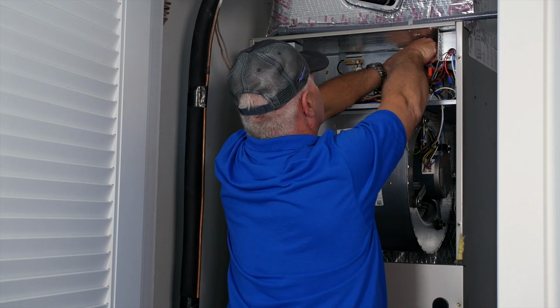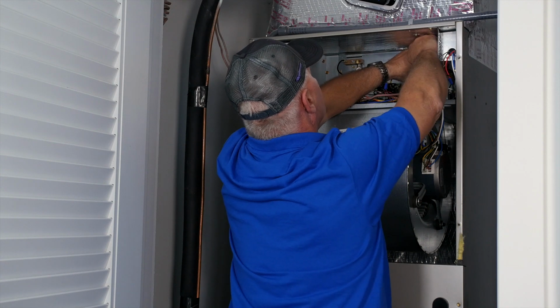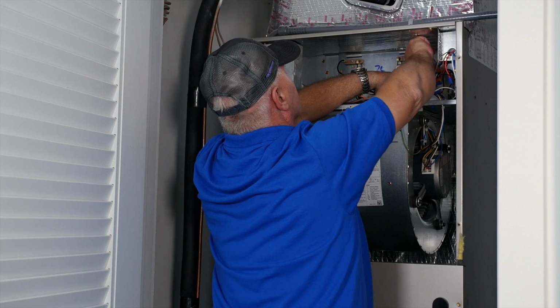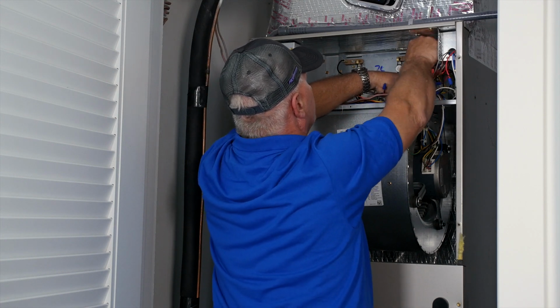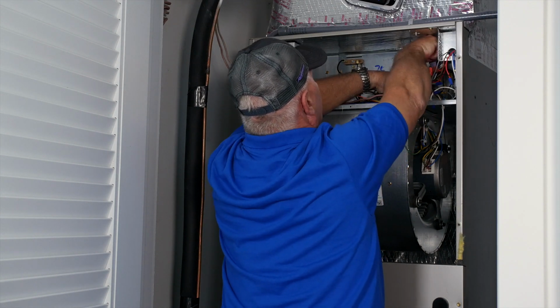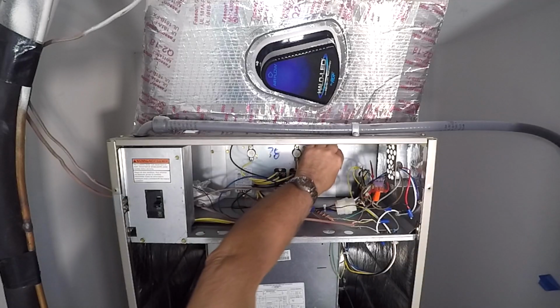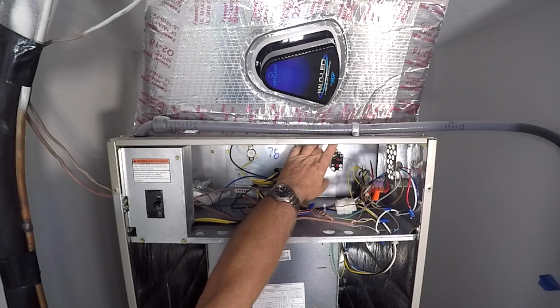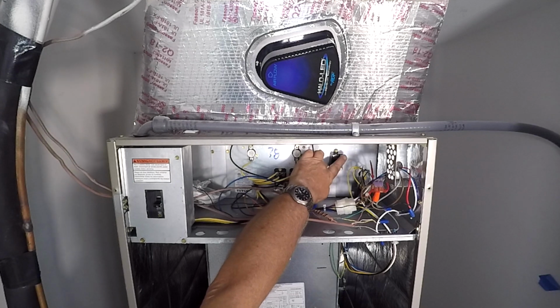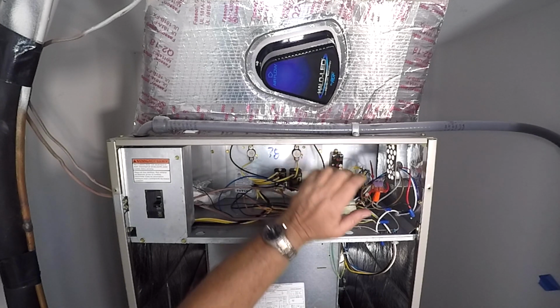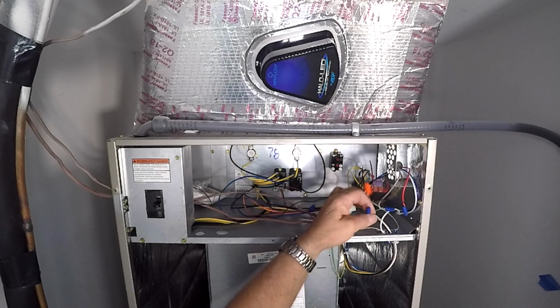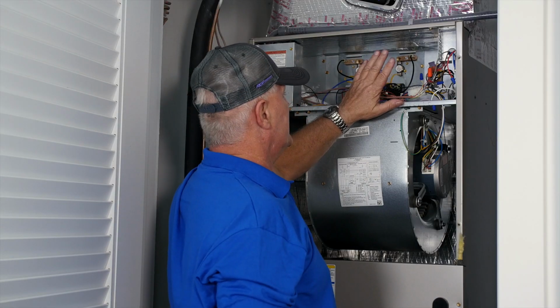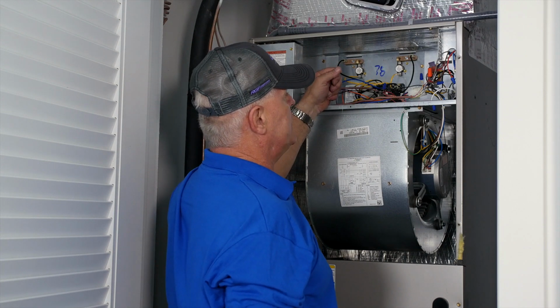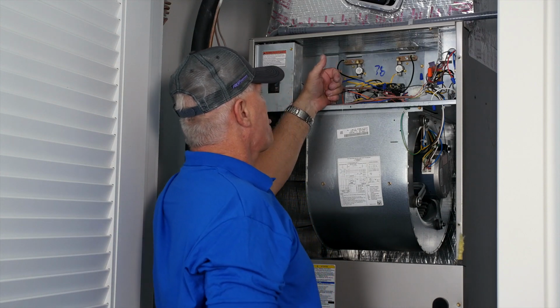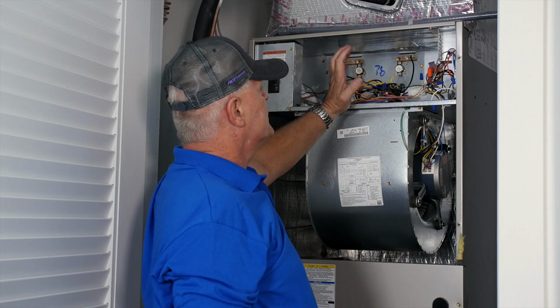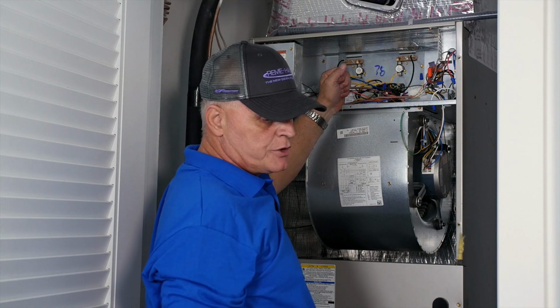On the relay, you will be able to see in a moment, there are 5 connections, 2 of which are low voltage for the coil of the relay to cycle it on and off. And we are going to cycle those through from the existing thermostat in the unit. So as I have the relay positioned here, you have terminal 3 and terminal 1. We're going to connect terminal 1 to the yellow wire connecting to the thermostat, which powers the condenser that will cycle the relay every time the outside unit turns on, and it will close the contacts between terminals 4 and 2. We're going to feed our power through this relay from terminal 2 and out terminal 4 to our transformer.